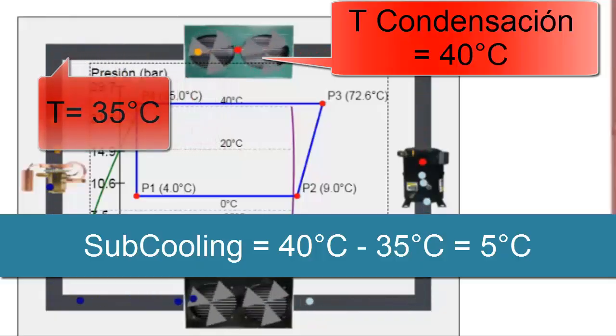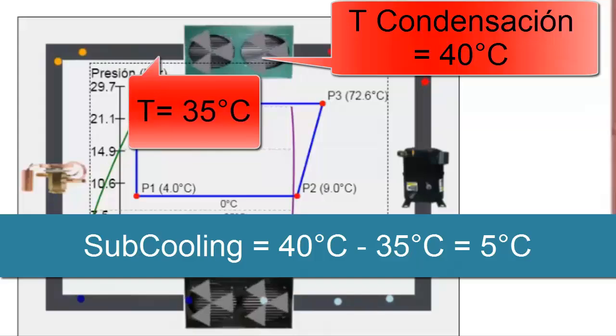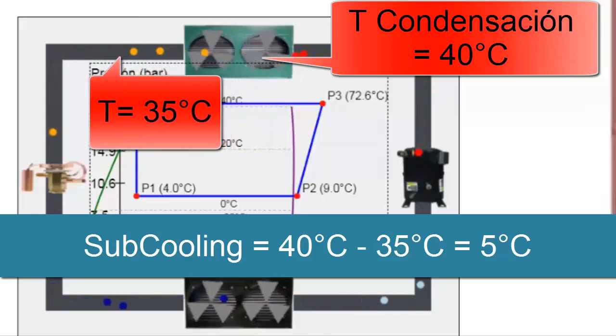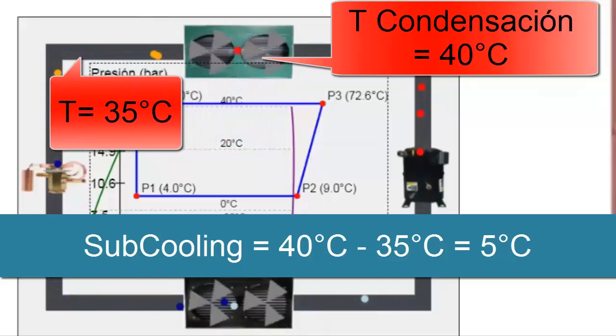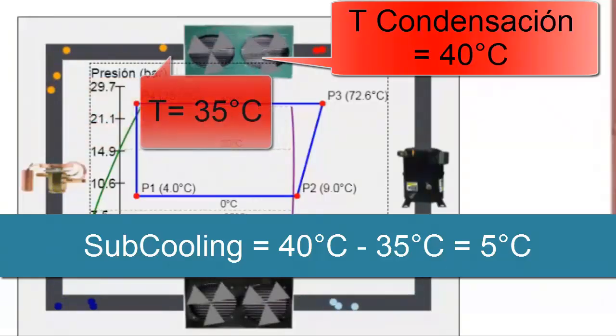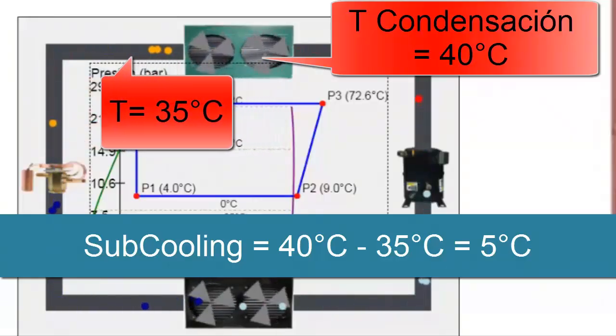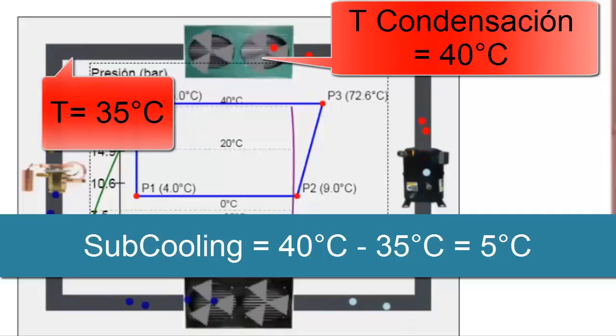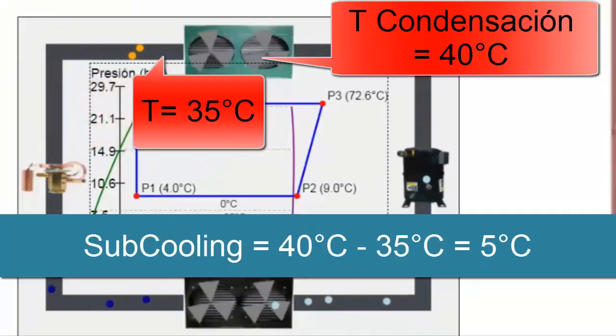However, it is important to note that in hot climates or under adverse thermal exchange conditions in the condenser, such as low fan speed or external dirt on the condenser coil, the sub-cooling may be less than 5 degrees Celsius, even dropping to 0 degrees Celsius.